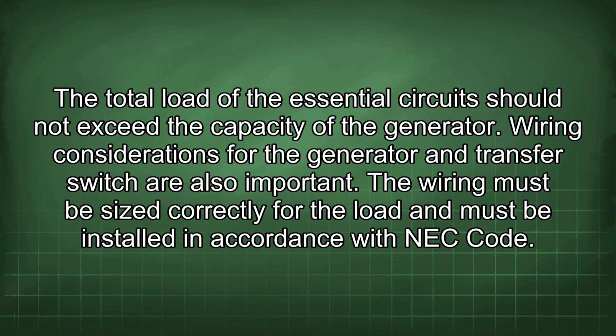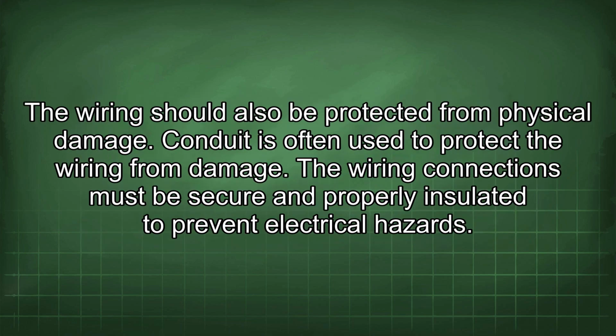Wiring considerations for the generator and transfer switch are also important. The wiring must be sized correctly for the load and must be installed in accordance with NEC Code. The wiring should also be protected from physical damage. Conduit is often used to protect the wiring from damage. The wiring connections must be secure and properly insulated to prevent electrical hazards.